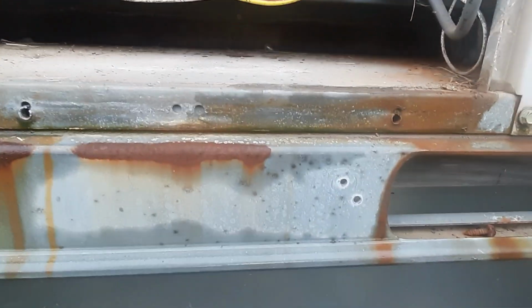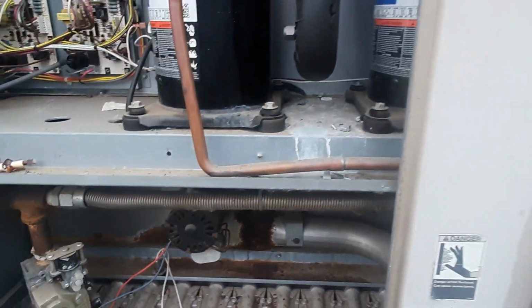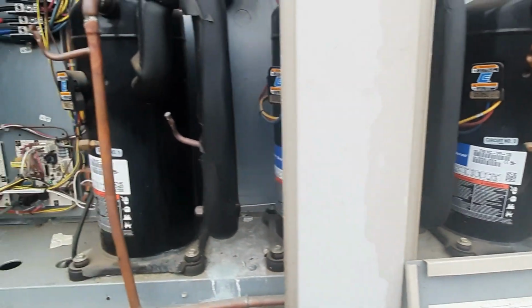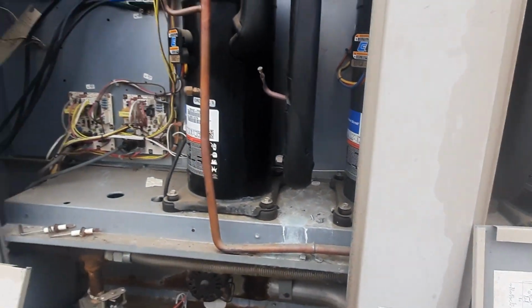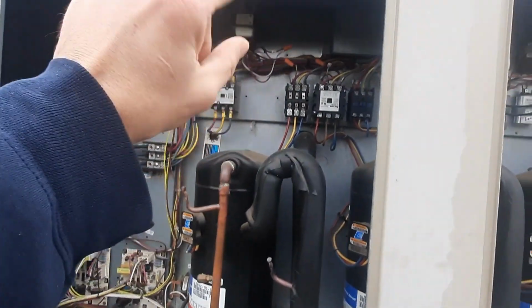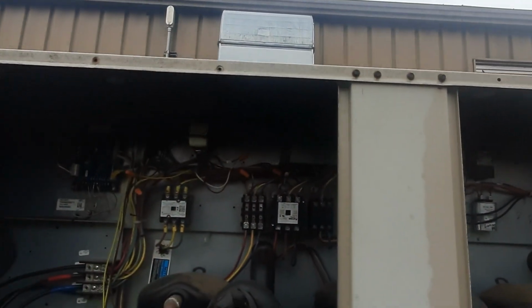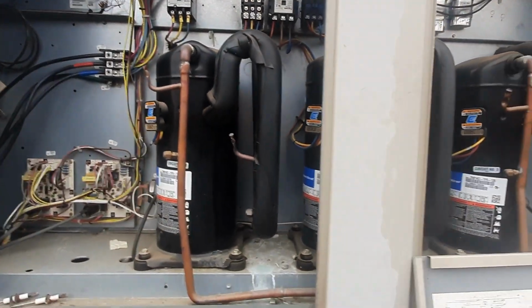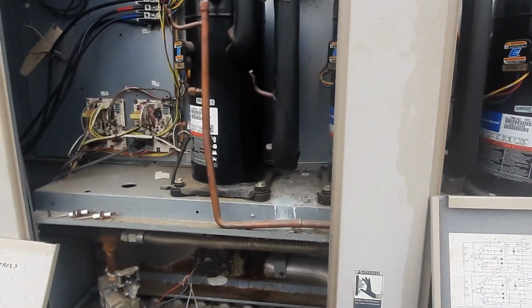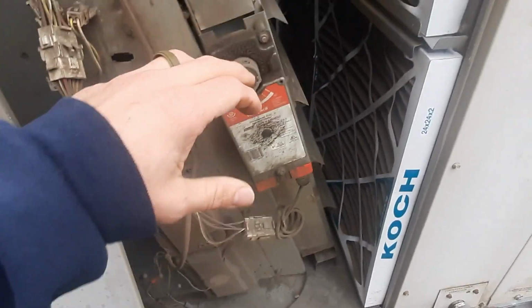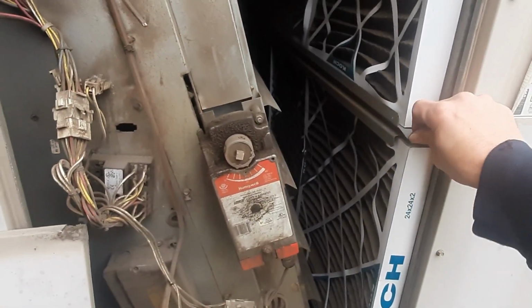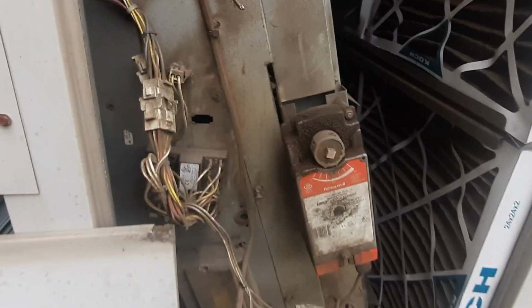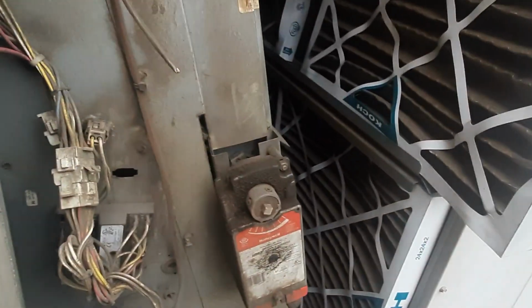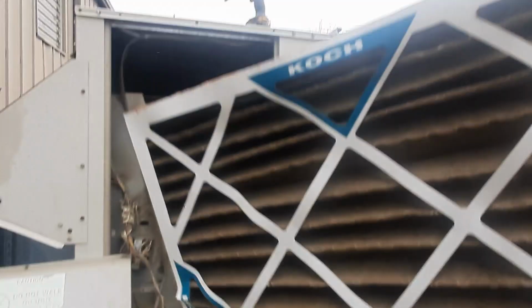So I'm not sure where the limit is on these. Don't see it in there. It must be in the blower section. Well, let's hunt the limit down and check our blower. Blower sounds okay. The duct runs probably 15 foot that way, and it's got a rack fan on the other end of it. Rack fan is running as well. So let's keep on digging. As you can hear, blower sounds okay, but what do we do 90% of the time? Airflow, airflow, airflow. These filters. Oh yeah. Take that out. Wonder why our limit tripped.